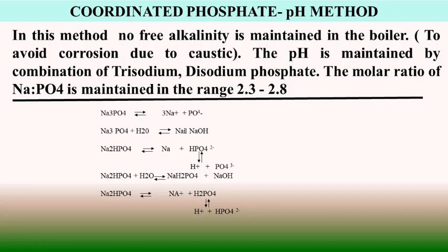This differs from the standard program in that phosphate is added to provide a controlled pH range in the boiler, as we have already discussed, within 11.2, and in the boiler water wall, as well as to react with the calcium if hardness should be avoided in the boiler. Trisodium phosphate hydrolyzes to produce the hydroxide ion, and that prevents the formation of scaling.